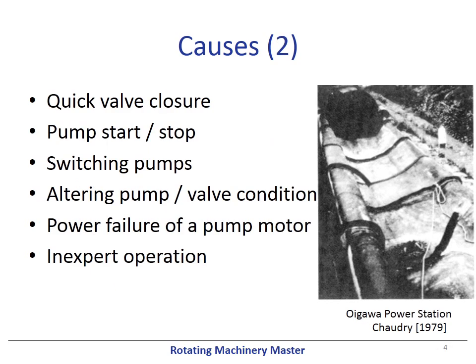These are examples of the origin of water hammer: a quick valve closure, a pump start or stop, switching pumps, altering pump or valve condition, power failure of a pump motor, or inexpert operation.